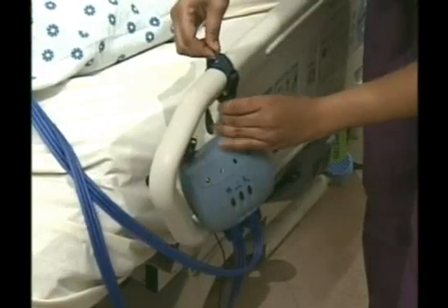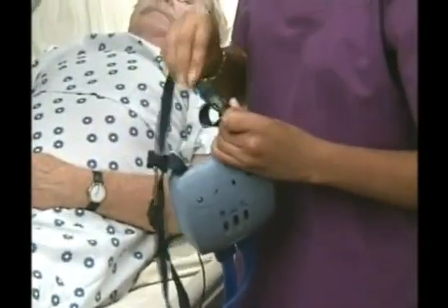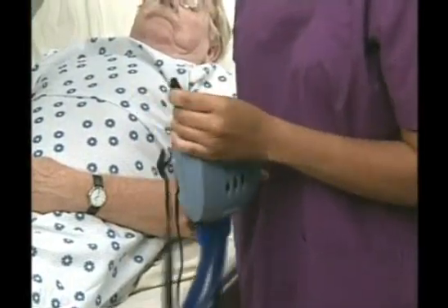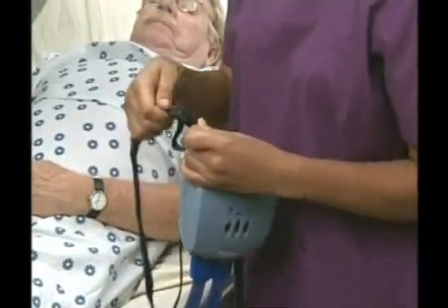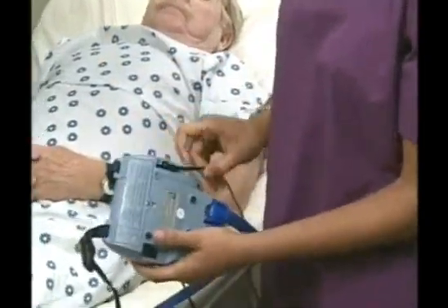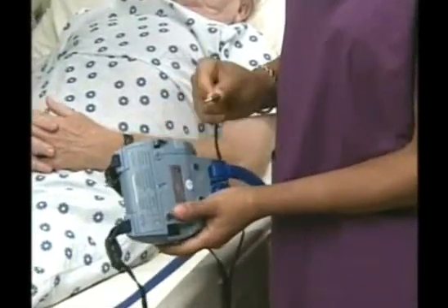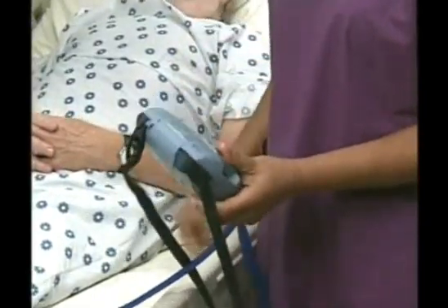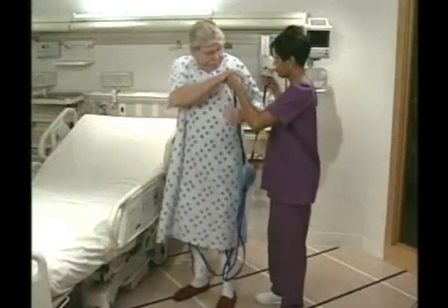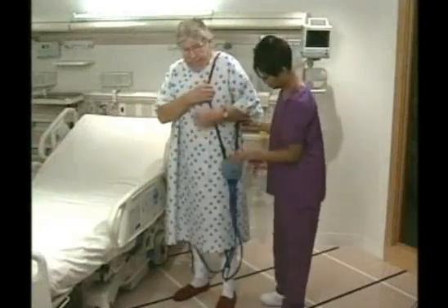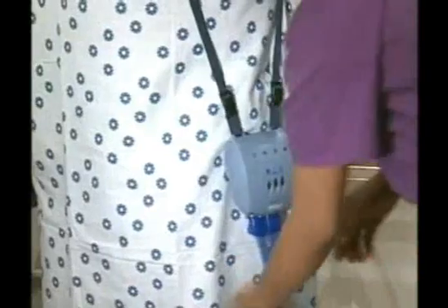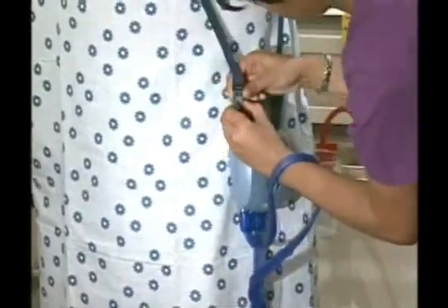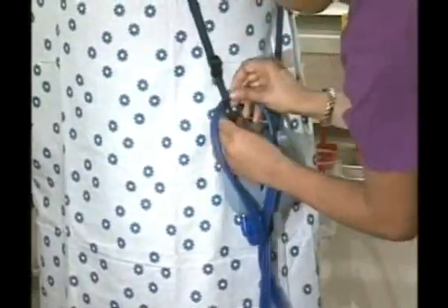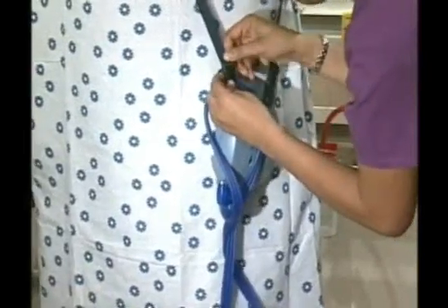The carrying strap for the ActiveCare DVT unit is designed to be used in a variety of ways. It can be configured for over-the-shoulder use during ambulation or attached to a bed, bedside chair, walker, or wheelchair. The strap can easily be converted from a short length to hang on a bed rail to a long length for over-the-shoulder use. When your patient is wearing the ActiveCare DVT system while walking, the extension tubing should be shortened to prevent tripping. Just loop the tubing through the clips on either side of the device, like this.